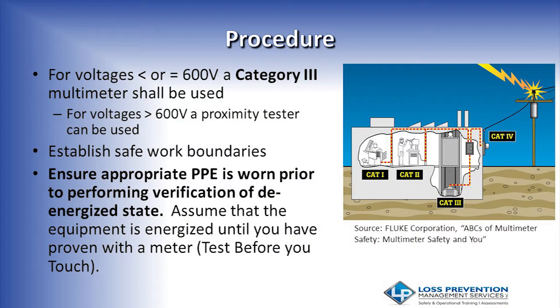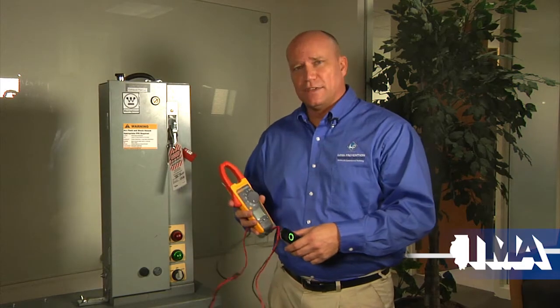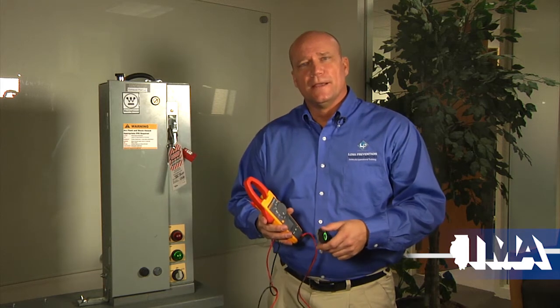That's very, very important. So let's go back to category. Category 3 is 3-phase industrial AC and 277 volt lighting. A category 3 meter is capable of withstanding either 6,000 or 8,000 volt surges, and a category 2, which is just for shop equipment, and a category 1 for electronics, may not be. So bringing that into your facility and doing a live-dead-live would not be a safe thing to do. That's really important.